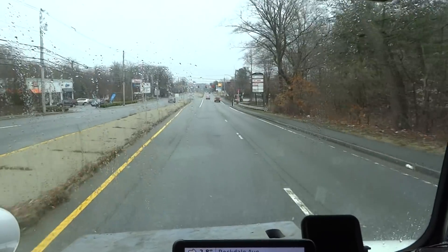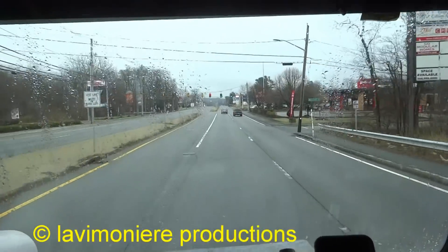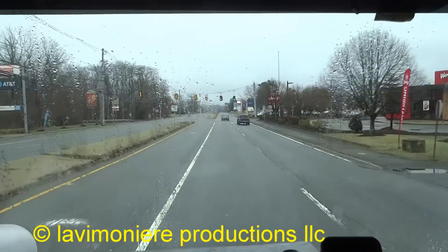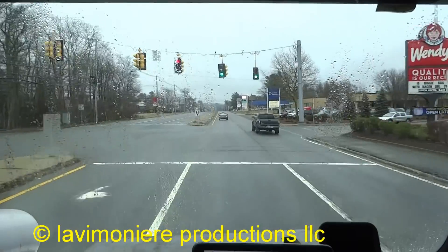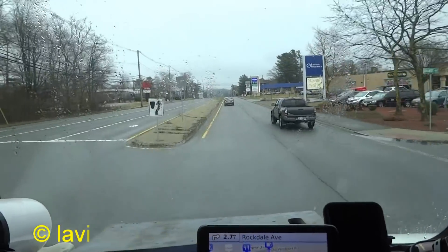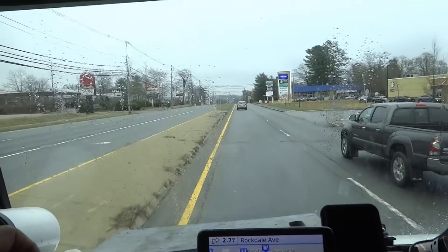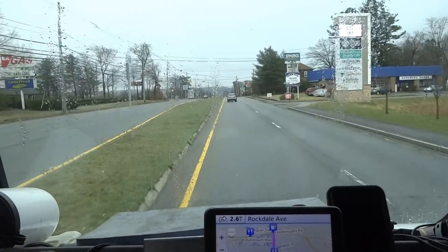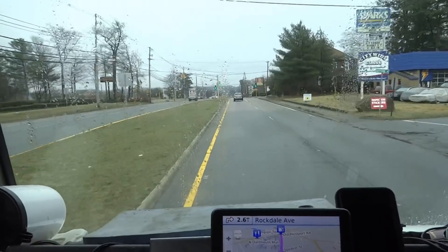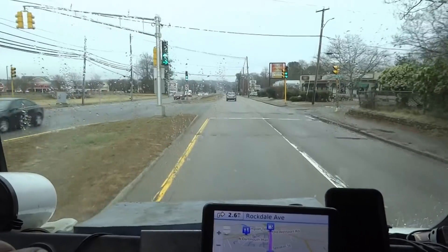Morning guys, it is April 6th, 2019, Saturday morning. They called last night for an oil boiler service. Once in a while, it's a tenant over there. She says the reset button tripped — the red light's on, she pushes the button and nothing happens. No power there, so that leads me to think it's a burner motor, bad cad cell, or a relay that's bad if nothing's spinning.